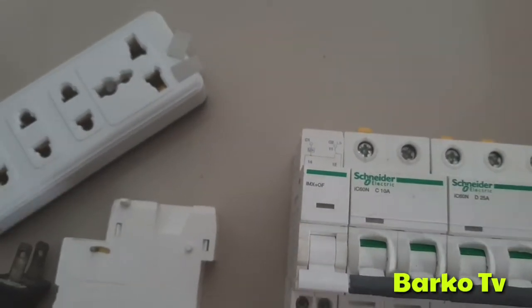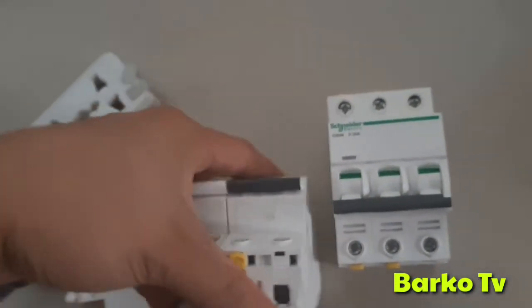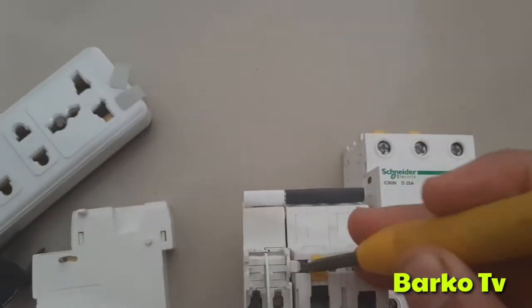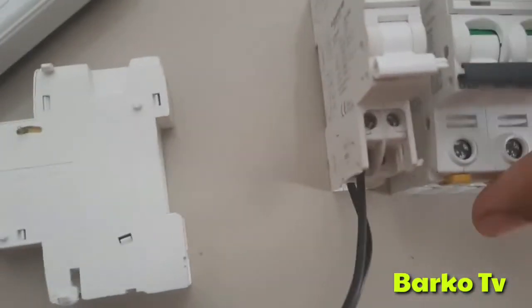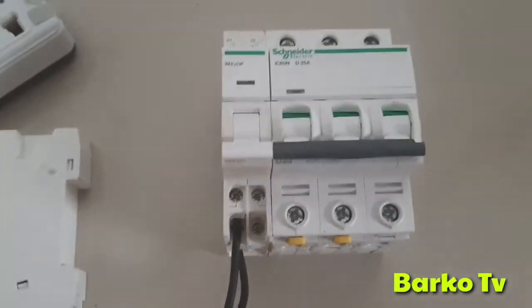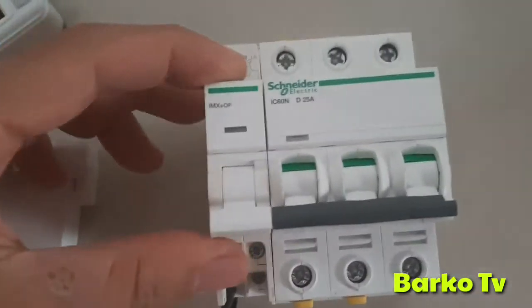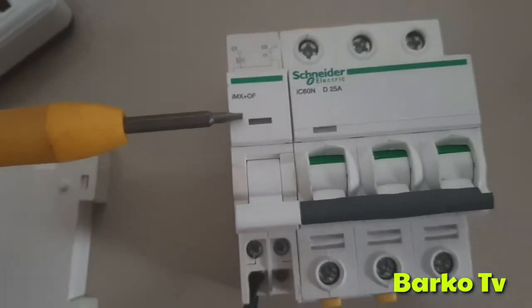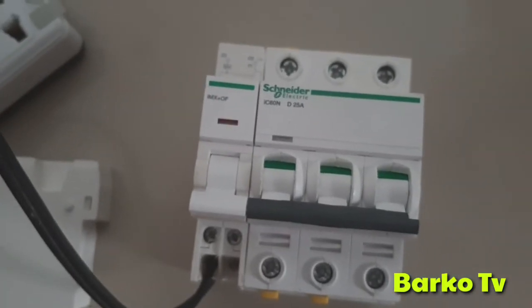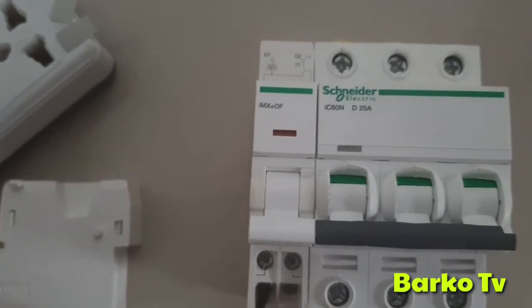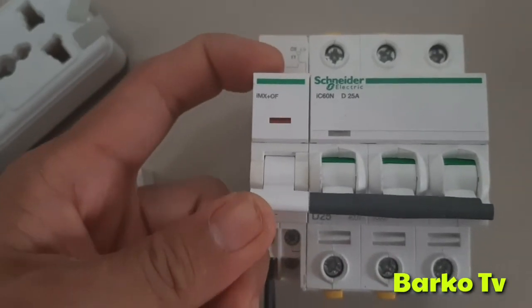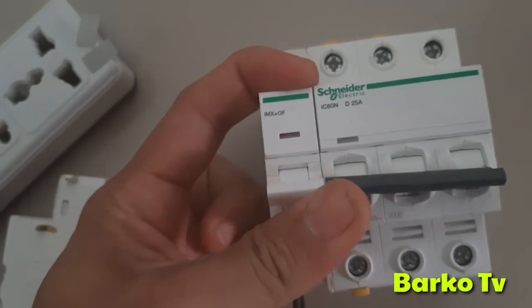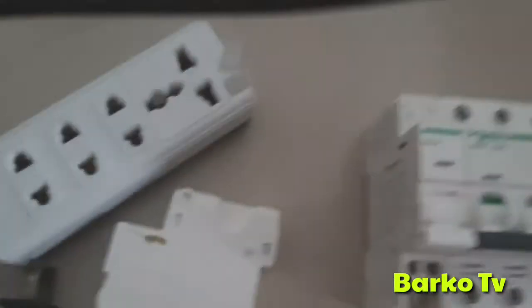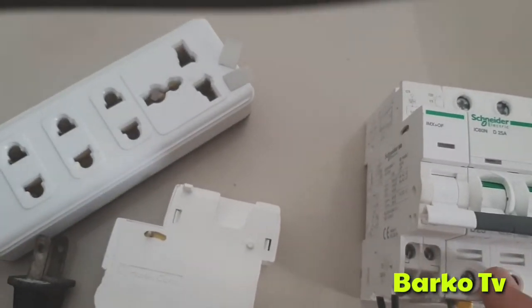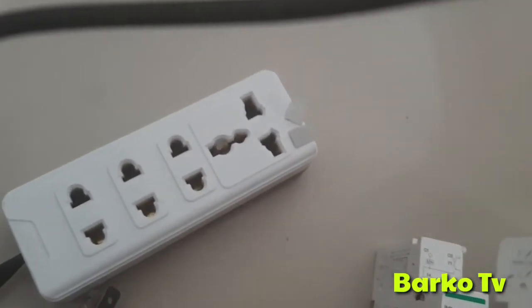This one is the setup in the panels. Also, we tried the three phase. In our design, the three phase is 440 or 220, it depends upon the supply, but normally the supply on the shunt trip device is 220. It depends upon your ship design, but in our ship design, this activates at 220. But our shunt trip device is capable of 110 to 415 volts AC or DC, and 100 volts to 130 volts DC.